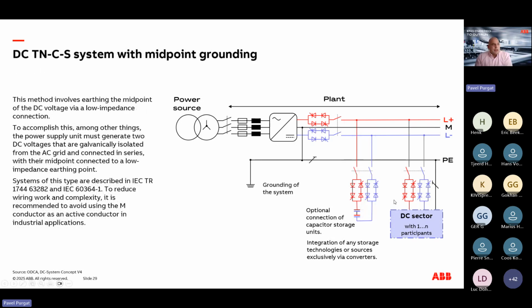The third option, and that is the most complicated, is using a midpoint that is grounded and loadable. In this case, we need a more complex protection devices. At the same time, we need to think about balancing of the voltages on both sides. Otherwise, equalizing currents will flow through the neutral, and the neutral might not be designed for such operation. That's why these systems are usually more theoretical, and in practice, the DC IT systems are dominating.